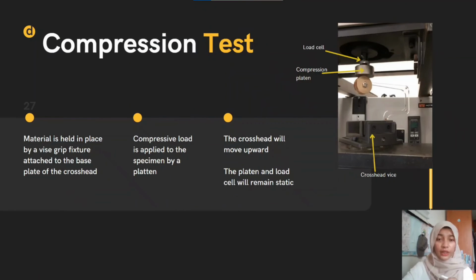Next is the compression test. During the compression test, the material is held in place by a vice grip fixture attached to the base plate of the crosshead. And then the compressive load is applied to the specimen by a platen, and the crosshead will move upward while the platen and the load cell remain static.